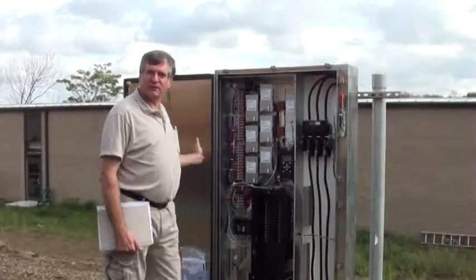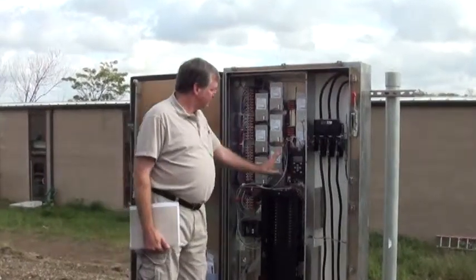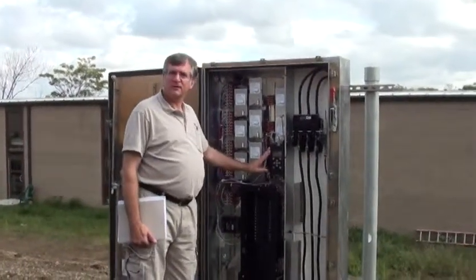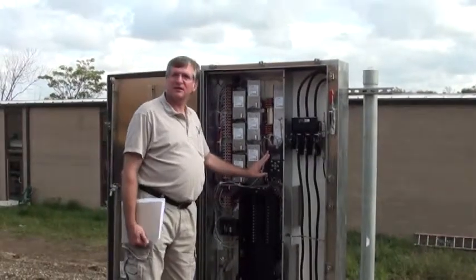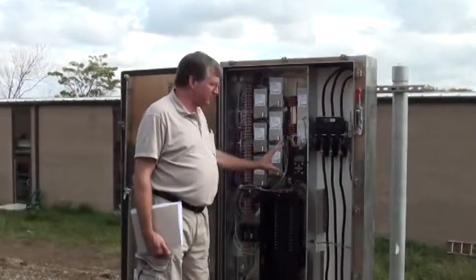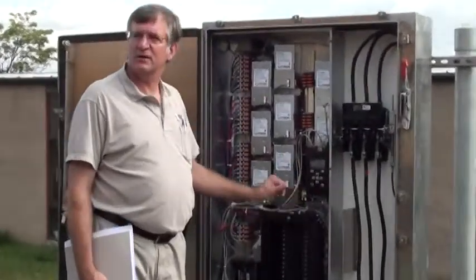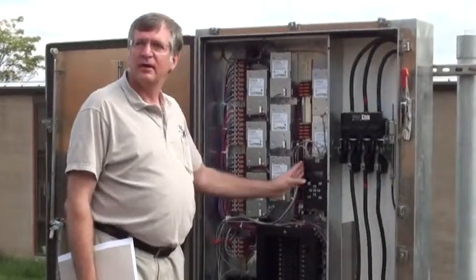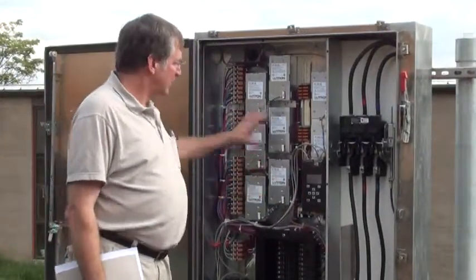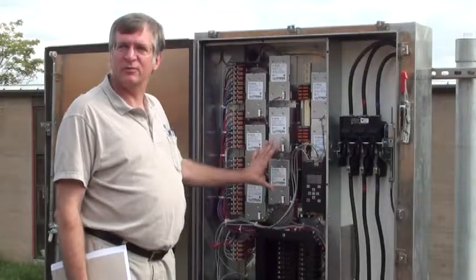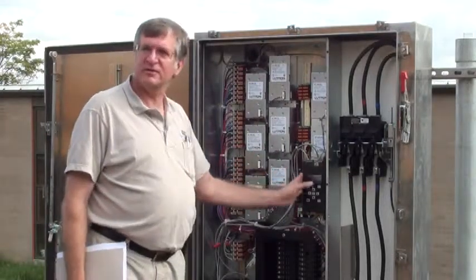All right, so this would be panel number 2. You still have a controller in here, but this is really meant for installation type work, where I can program this unit on where it sets into the network, tell it that it's number 2, and tell it where it starts in the count. The unit's a little bit bigger - it has 32 relays in it.